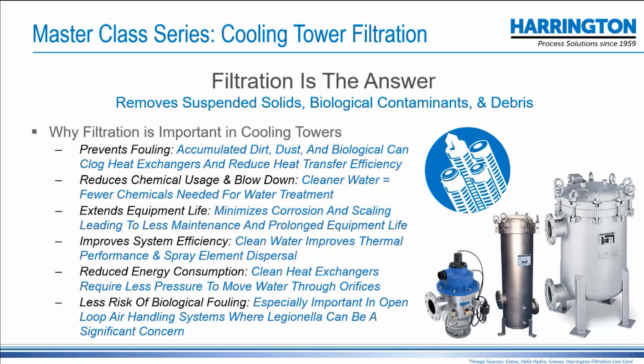If you don't have sludge, you don't have to open a valve and drain the basin of the cooling tower. You can almost eliminate blowdown as a factor. It'll extend the equipment life. It'll improve efficiency. If you don't have dirty spray nozzles and dirty dispersing elements, then your cooling tower is going to be that much more efficient. If your heat exchanger in the building is not clogged, you're not going to have to shut it down and force feed air and water through it to get it open. And it's going to preserve the life of your equipment.